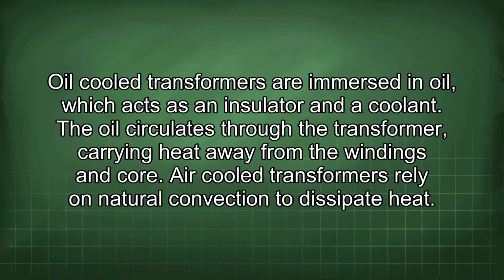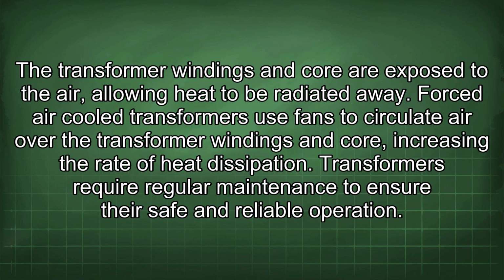Air-cooled transformers rely on natural convection to dissipate heat. The transformer windings and core are exposed to the air, allowing heat to be radiated away. Forced air-cooled transformers use fans to circulate air over the transformer windings and core, increasing the rate of heat dissipation.